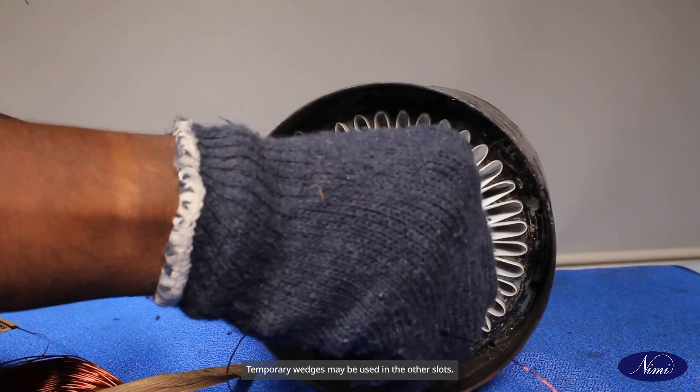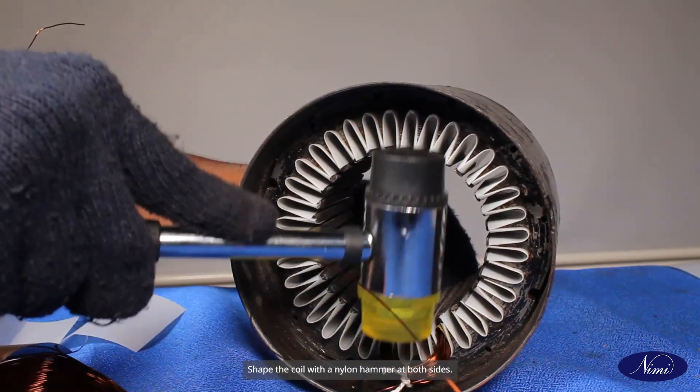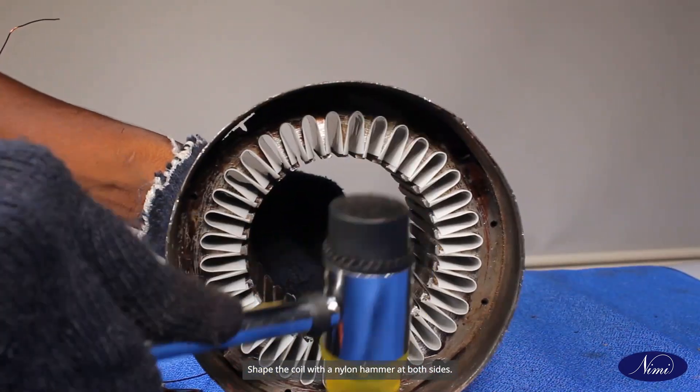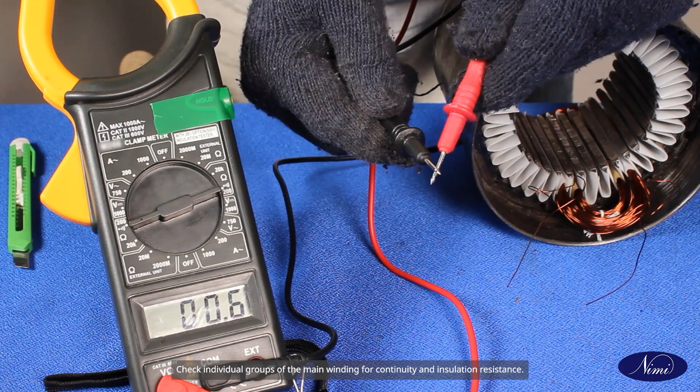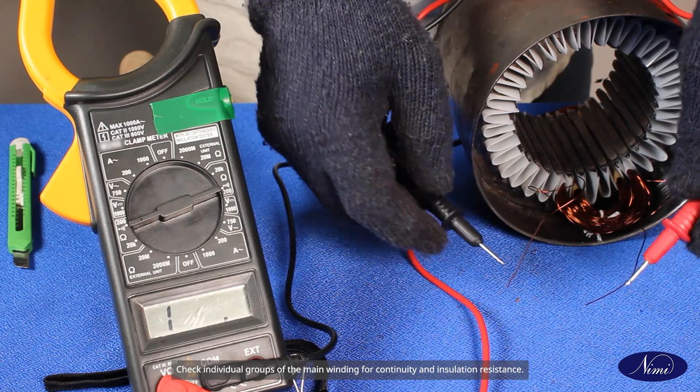Temporary wedges may be used in the other slots. Shape the coil with a nylon hammer at both sides. After placing all the main winding coils, check individual groups of the main winding for continuity and insulation resistance.